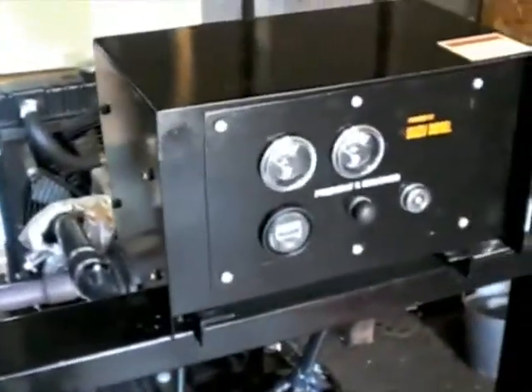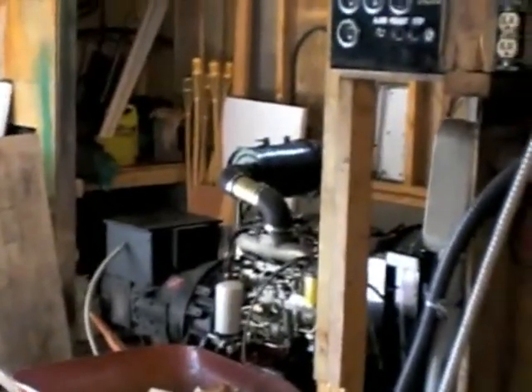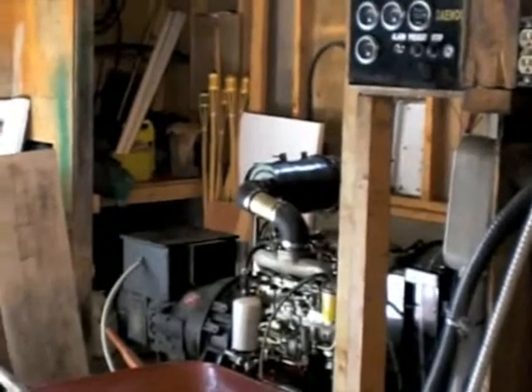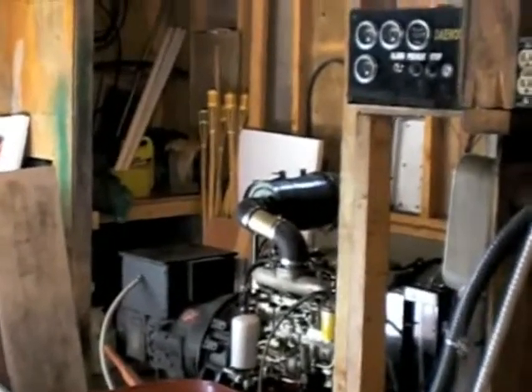Of course, we have wires leading to the battery on the generator, and some wires leading to the ignition box on the generator as well. This here is where the power for the generators gets fed into, and I say generators because this is a double throw switch. They also have a 20 kilowatt Daewoo engine over here, which is now on standby, and it's not hooked up to the remote control or the control module. And we've noted on a couple of the devices down here that the generator auto starter must be disengaged if we're ever trying to service the generator, so just for safety.